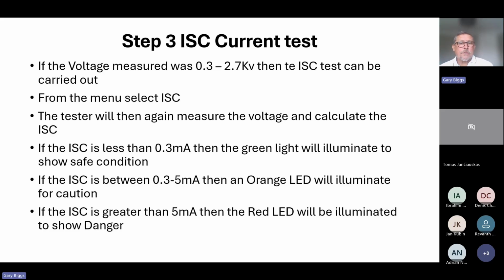We're measuring at the cross arm, which gives you a potential of up to 5 milliamps, for example. But it means that as you go higher up the pole, that potential voltage, and therefore the potential short circuit current, will become higher, and the higher up the pole you go, the more danger you potentially can see. If the ISC is greater than 5 milliamps, then the red LED will light to show danger, because 5 milliamps or more of current is a level perceived to be dangerous to human beings, so if that is detected, it will show danger.